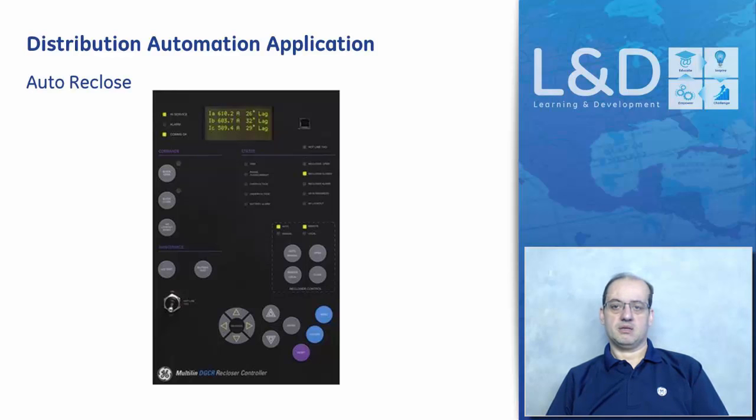So the common stories in the field are a branch falling on a wire, or any animal shorting phases and stuff like that. So basically, these applications can look for certain primary equipment signals, digital inputs, digital outputs, analog inputs, and then based on these values, they would of course cause dead time, which is the time between circuit breaker trip and automatic reclosing of the circuit breaker, to check that the protection status has been achieved.